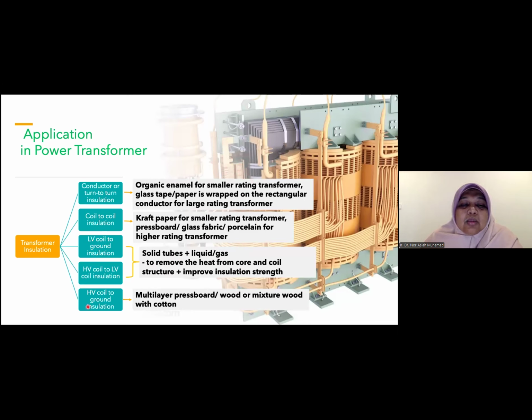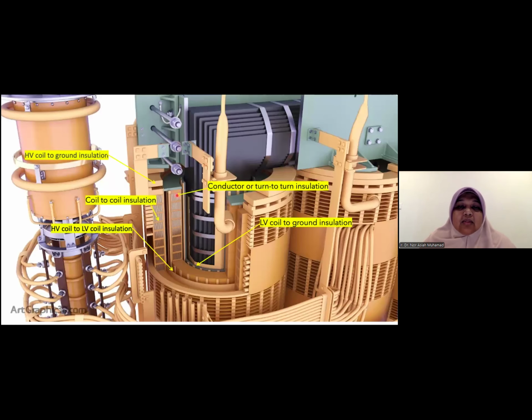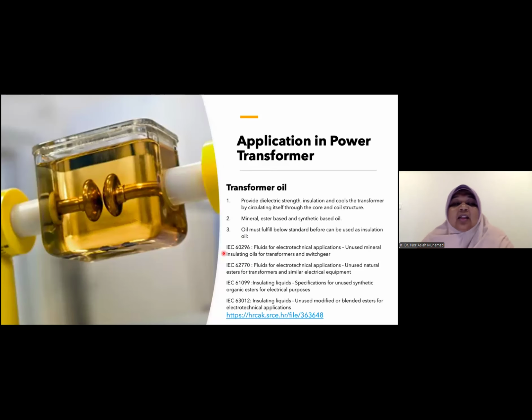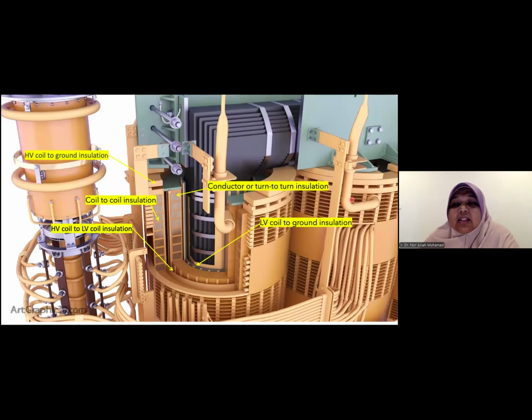Then to improve the strength, we have high voltage coil to ground. We have high voltage coil to ground at the bottom, because most of the tank is grounded. So here is the insulation between the active component, which is the winding, and the tank, to prevent short to ground. Maybe here we can look at it closely. We have turn-to-turn, phase-to-phase, so the conductor or turn-to-turn insulator. Then we have low voltage coil to ground. Here we have high voltage to low voltage, this is low voltage, this is high voltage. We have the insulating material here and also oil inside here. We have coil to coil, then we have high voltage to ground. So this is the major insulating material or insulating system. This is all the solid insulator inside the transformer.